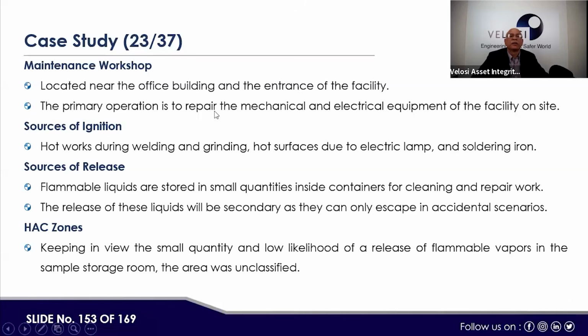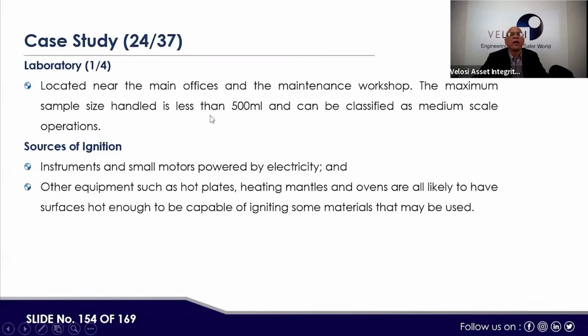The primary operation is to repair the mechanical and electrical equipment of the facility on site. Hot work during welding and grinding, and hot surfaces due to electric lamps and soldering irons, are the sources of ignition. Source of release: flammable liquids are stored in small quantities inside containers for cleaning and repair work. The release of these liquids will be secondary, as they can only escape in an accident scenario. HAC zone: keeping in view the small quantity and low likelihood of released flammable vapors, the area was unclassified.